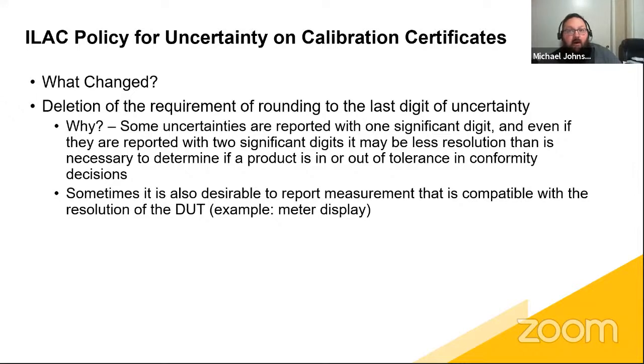That allows Metcal to never report an uncertainty lower than your CMC when taking that approach, because you'll always have a repeatability included in the calculation. That relies on making sure everything else that goes into your CMC is included, which may mean including specific contributors that aren't automatically done by a given FSC, making sure you're including those additional contributors to cover it all in that same calculation. But as long as you include all those contributors, and use that CMC approach with zero repeatability, you're never going to report a lower uncertainty with Metcal.